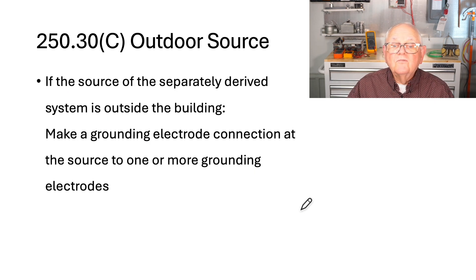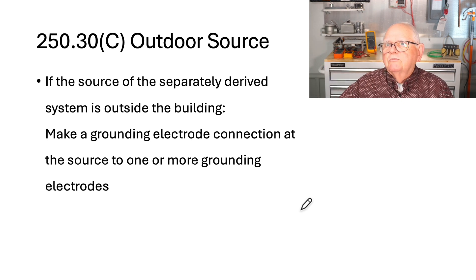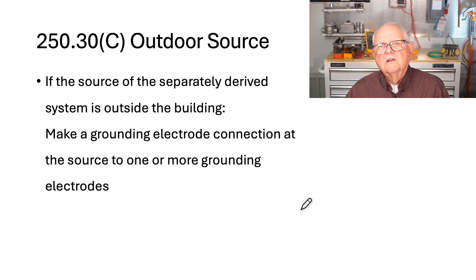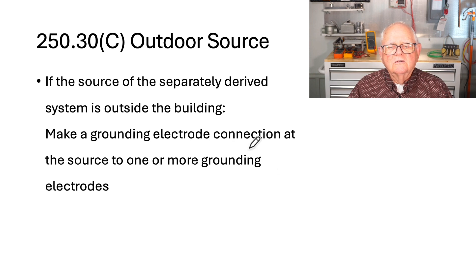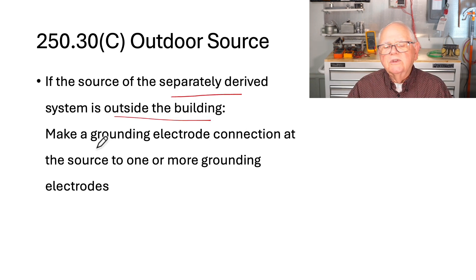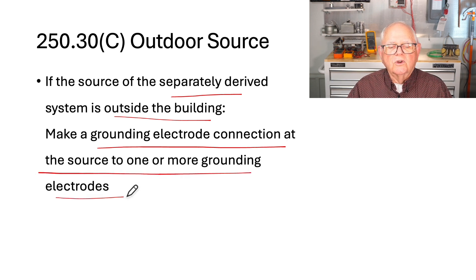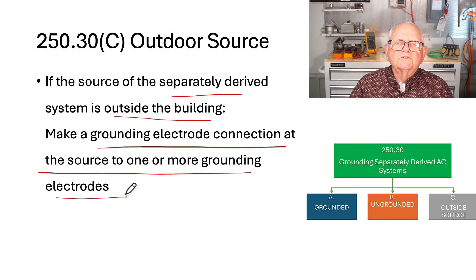Finally, what if the source is an outdoor generator outside the building it's serving? That's considered an outside source. Where do you have to ground it? At the generator itself. If the source of the separately derived system is outside the building, you make a grounding electrode connection at the source to one or more grounding electrodes. That, in a nutshell, covers the rules for grounding and bonding a separately derived system.